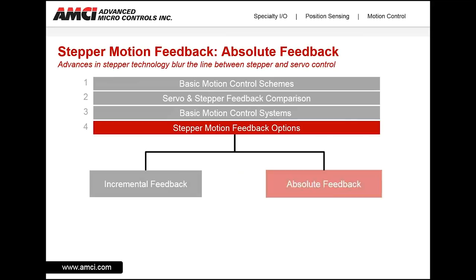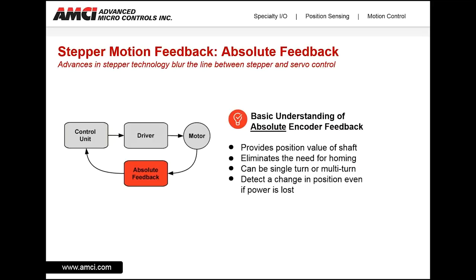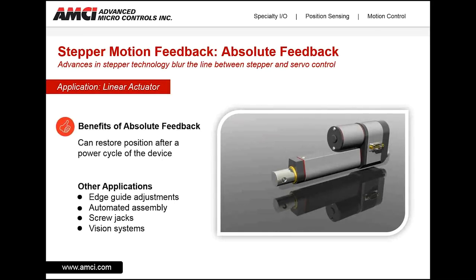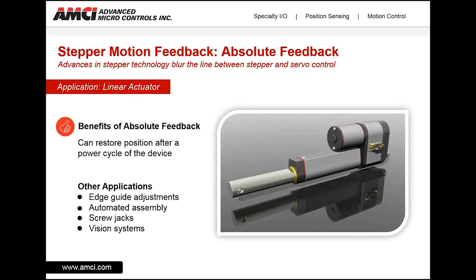Now for absolute position feedback. Absolute encoders provide the position value of a shaft — they know where the shaft is at any given point in time. Because of this, they can eliminate the need for homing on power-up and in-between move cycles. The absolute position feedback can be either single turn or multi-turn, and it can detect a change in position even if power is lost. Absolute encoders are ideal for linear applications. As the motor shaft rotates clockwise and counterclockwise, the control unit continuously monitors the motor shaft position. If power is lost, the absolute encoder can re-establish position of the linear actuator once power is restored, eliminating the need for a home cycle on every power-up.